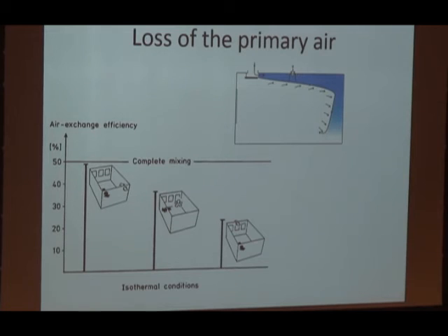So these two systems to the right, they do not work as ventilation systems. You should not pay for these kinds of systems. They do not at all fulfill decent requirements. And this, I call it isothermal conditions, because here you have a loss of primary air. What you supply goes to the extract ducts and doesn't go into the occupied zone. So there's no use of this lost air.